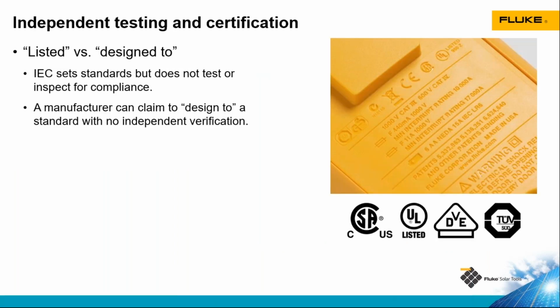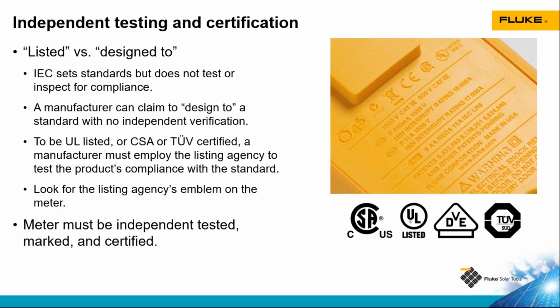When manufacturers design test tools, they design them to certain standards. These standards set how the tool needs to withstand these transient voltage spikes. And we at Fluke have these tools tested by a third party to ensure the tool actually meets the requirements of that standard. Not all manufacturers do that. Some manufacturers will design to a specific standard, but they don't actually have it third-party tested. And without that third-party testing, you don't know if the tool will actually meet those requirements.